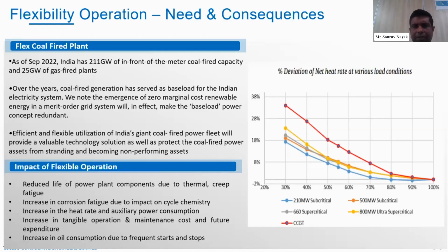What is the impact of the flexible operation? Flexible operation of the thermal power plant will have a large impact on the plant life because of the different thermal and creep fatigue of the equipment. There will be some corrosion fatigue due to the cycle chemistry. There will be an increase in the heat rate, and auxiliary power consumption will also increase. There will be some tangible operation and maintenance cost, and it will also call for some future expenditure. The oil consumption in the part load condition will also increase due to frequent start-stop.